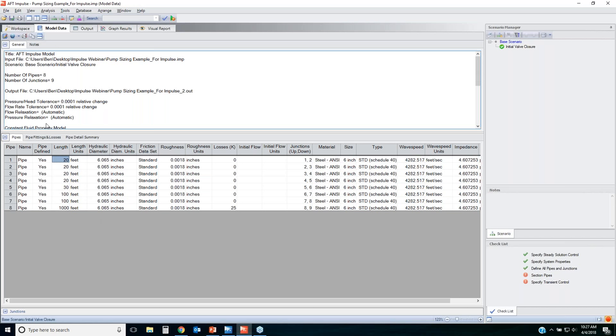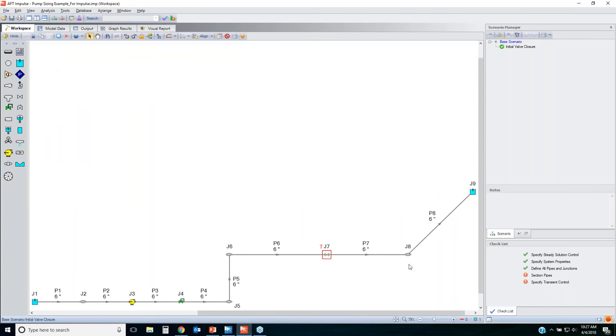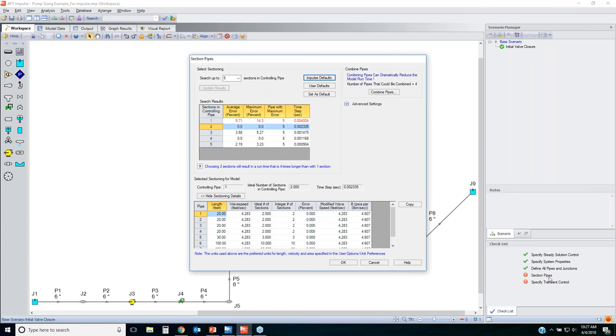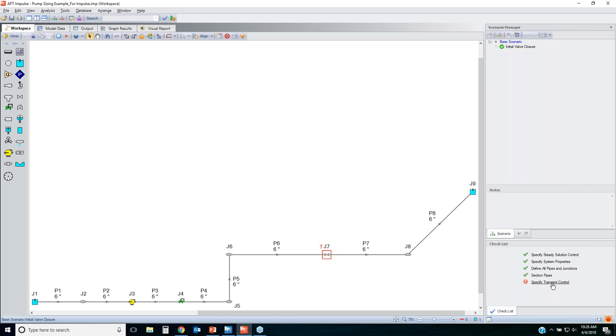When breaking all pipes up into bits, Impulse will break them into equivalent lengths of 20 feet if using one section in the controlling pipe; two sections in the controlling pipe gives 10-foot segments in every pipe. The more sections you have, the longer your runtime — so avoid really short lengths of pipe. To section my pipes, I click the link in the checklist and go with two sections in the controlling pipe. This gives a time step of two milliseconds — very fine resolution for analyzing the water hammer.